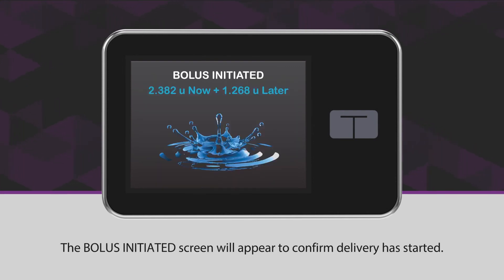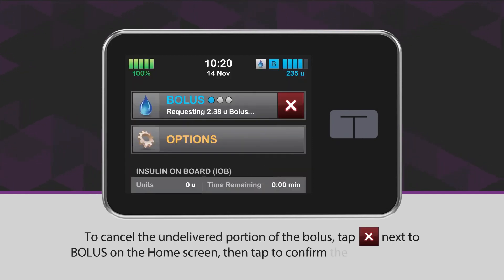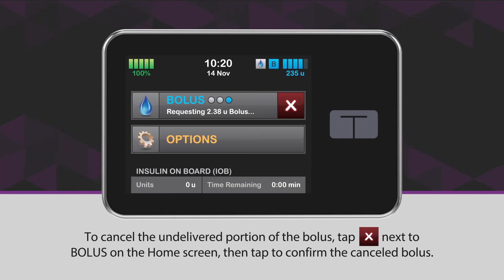The bolus initiated screen will appear to confirm delivery has started. To cancel the undelivered portion of the bolus, tap the white X icon in the red square next to Bolus on the home screen, then tap to confirm the cancelled bolus.